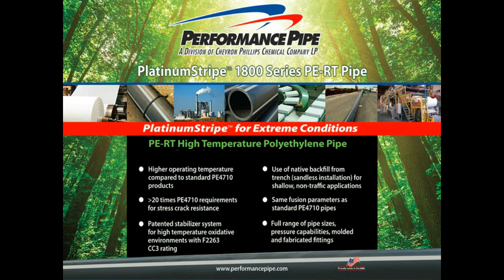Another question is, what is the largest diameter of the 1800 series available? As with the project that Wes touched on, that was a 30-inch diameter pipe that we've made, 30-inch DR21. I believe that we promote that we can produce up to a 42-inch diameter PERT. It's going to be limited somewhat on the DR because the wall thickness is going to be limited to maybe just a little bit over 2 inches, which would be the thickest that we can make.